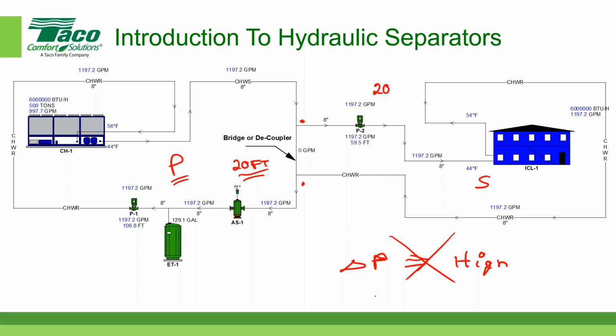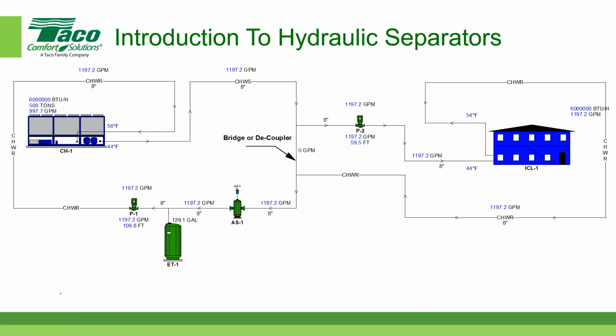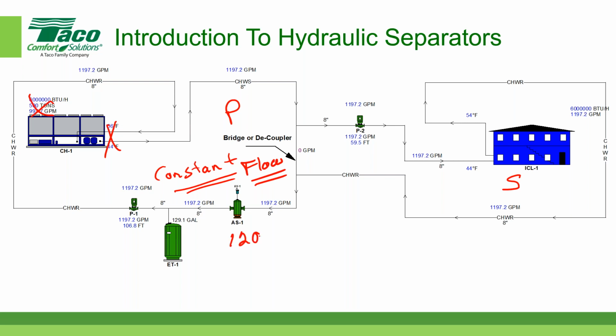Does that help? Yep. And someone's asking, when would the second case actually happen? That's fairly common. So again, let's go back to the primary circuit, and let's go to the secondary circuit here. Typically the primary circuit is constant flow. And in a primary-secondary circuit, back in the day, when chillers and boilers, and again, these numbers here are not correct, but chillers and boilers, in order for them to operate successfully, they had to have a constant flow. And so the purpose of the primary circuit was to maintain constant flow, and that's 1,200 gallons per minute.